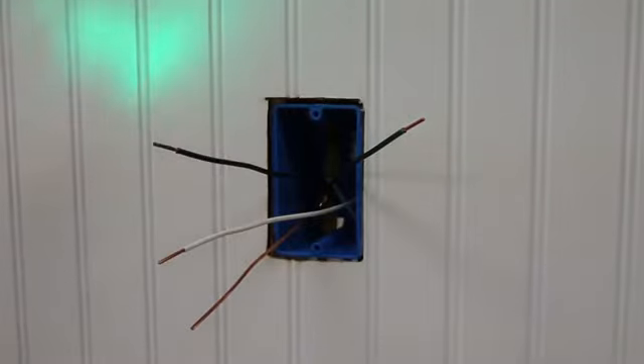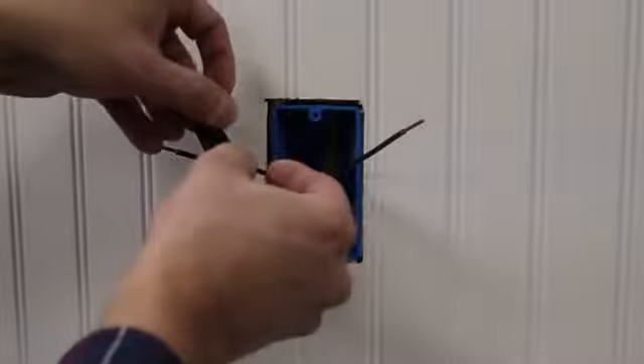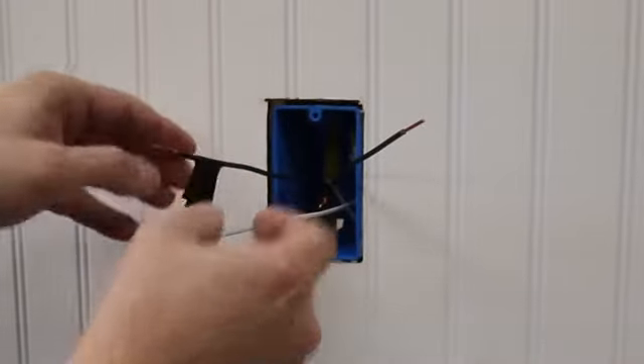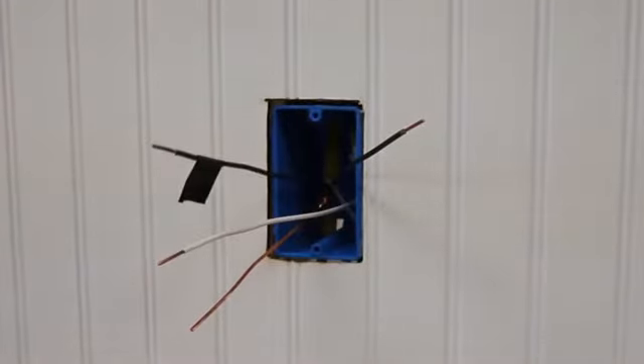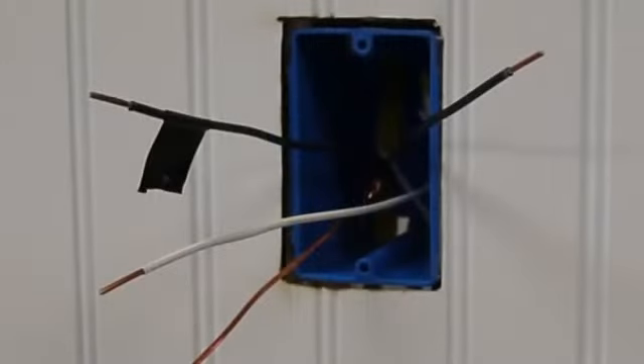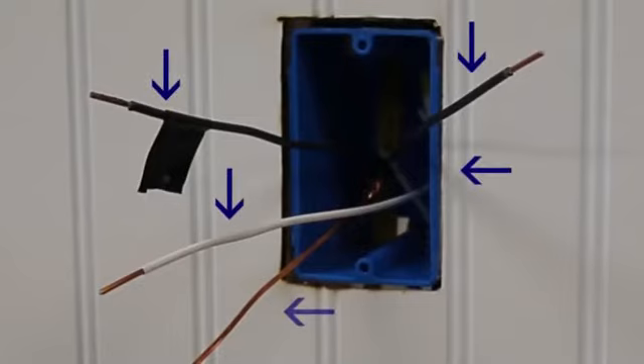Identify whether the wiring application is single pole or a three-way application. If wiring in the wall box does not resemble either of these configurations, please consult an electrician. We will begin with a single pole application. Please note that in this example, there is a black hot line wire, a black load wire, two white neutral wires, and a bare copper wire, which is the ground.